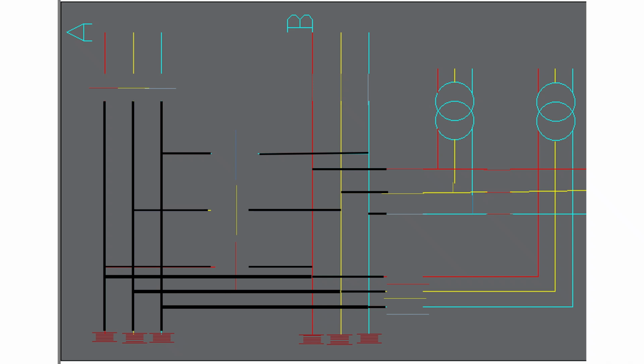But before that, you have to close the second isolator on the transformer side. If the phase sequence and parallel running of the two is not possible, then a power interruption is a must to change over. Normally it is not done that way. Without power supply interruption they are changing. First they change the power supply of one transformer, then the other, so that one transformer can give the power supply. But how to achieve this?